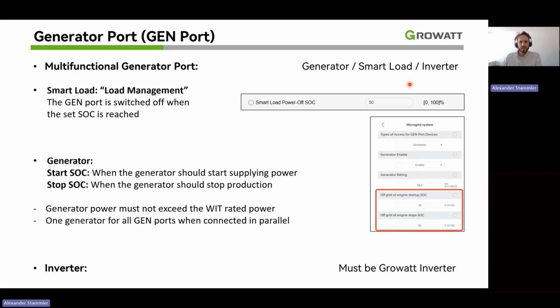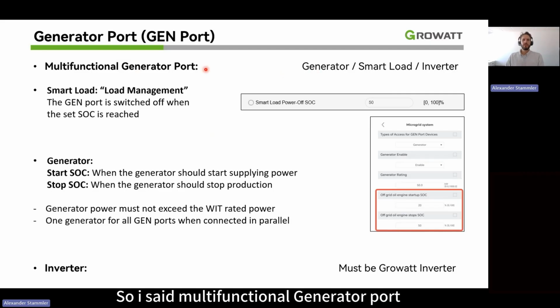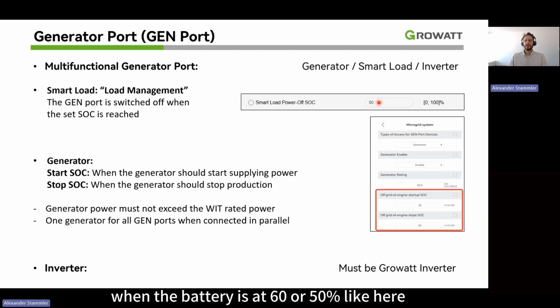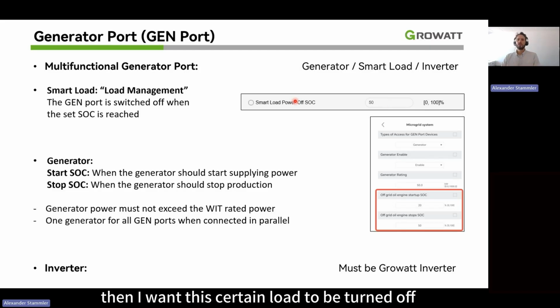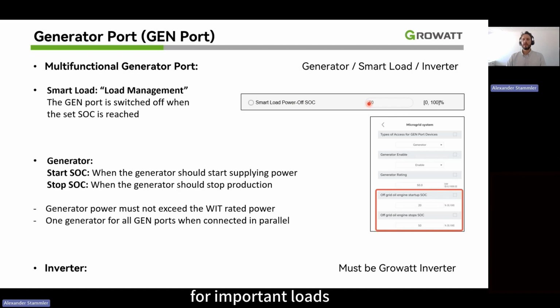So let me go one moment. Here I will go a little bit more into detail on what the generator port can do. I said multifunctional generator port, it can connect a generator. It can connect the smart load and the inverter. If you use a smart load, it is load management, meaning if you had a blackout, then you have, for example, some loads that you say are nice to have, but not necessary. So for example, you set in a value when the battery is at 60 or 50%, like here, then I want this certain load to be turned off. So it's load management. It says the battery is down to 50%, now the heating pump or so is turned off, because otherwise I need the rest of the capacity for important loads.